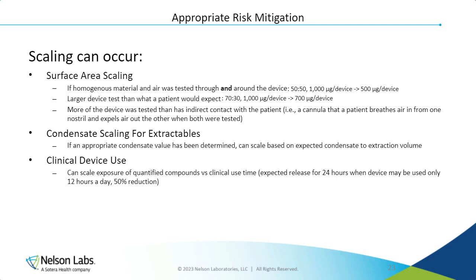We could think of a cannula that a patient can breathe air in from one side and then expel air on the other side, meaning only one side of the cannula will be used for breathing. However, the whole device was tested. The non-patient exposure may only account for a small percentage. We will just say 15% is the non-patient contacting, making our scaling factor 85%, just for easy math. This will lower that exposure seen to 850 microgram per device.